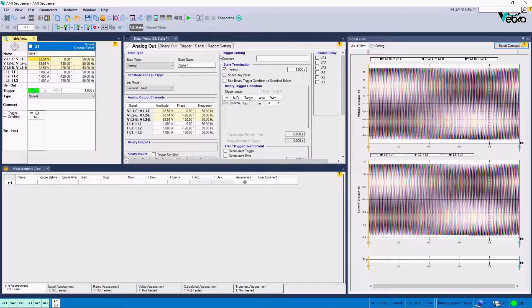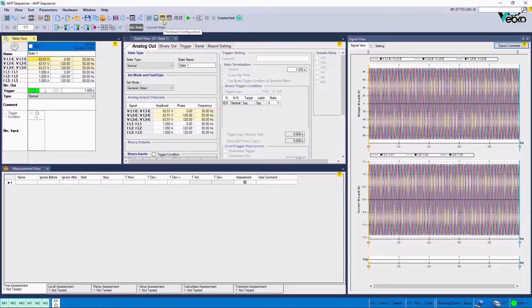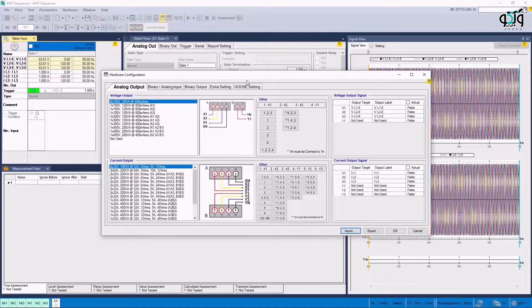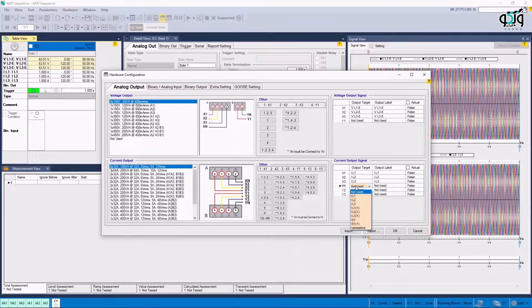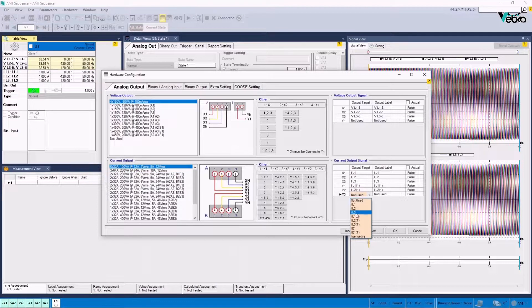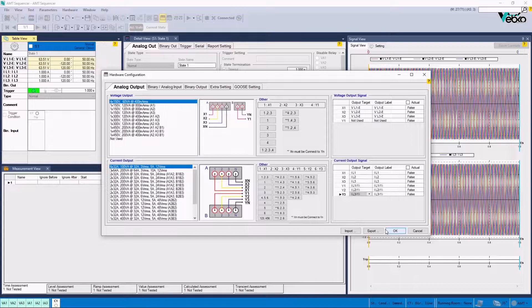At this point, the user needs to prepare the conditions for injecting values from both sides. It is possible to do so by selecting Hardware Configuration and specifying two current groups in Current Output Signal section. Here, the first set is indicated by IL1, IL2 and IL3, which are located in front of X3, X1 and X2 elements, respectively. Now, the second set is activated in front of Y3, Y1 and Y2.